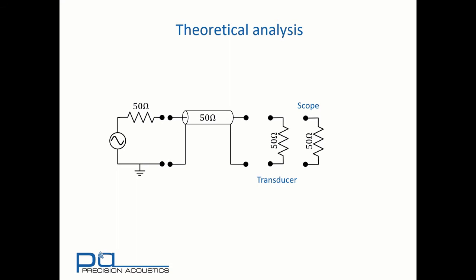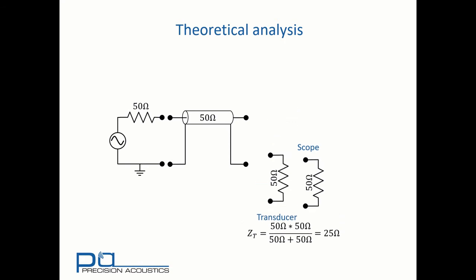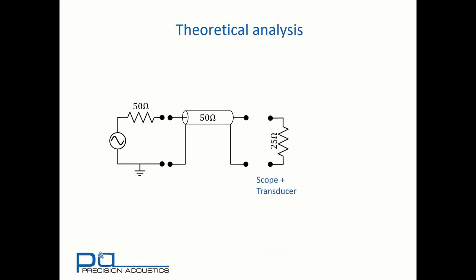when we use the T-piece and connect another 50 ohms to it, you can see in this situation we've actually got two 50 ohms in parallel. The net effect of that is to give us 25 ohms. At this point, we're effectively loading the scope-transducer combination onto a transmission line in a mismatched format. In this case, we would get a reflection occurring at this interface, and we would end up seeing not all of our signal developed across either transducer or scope.